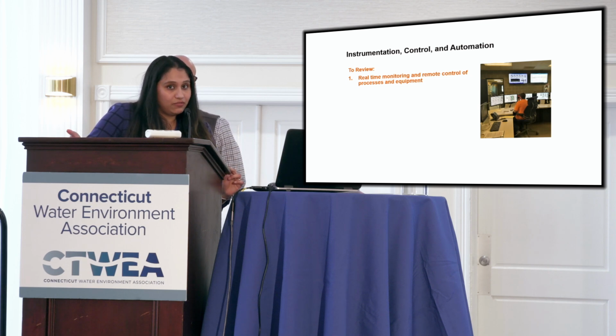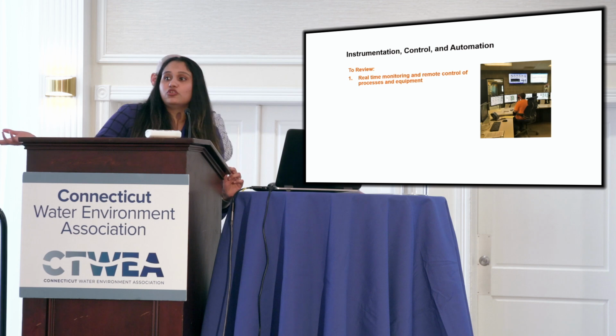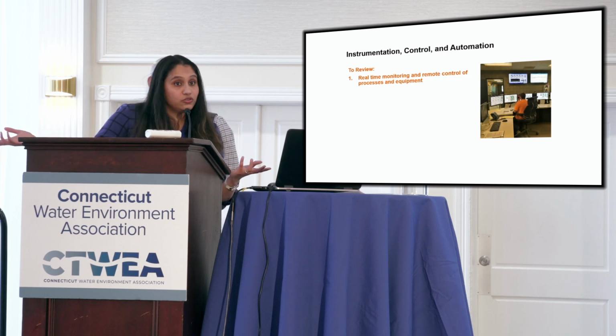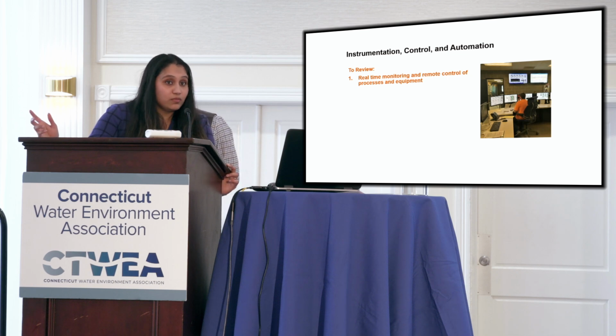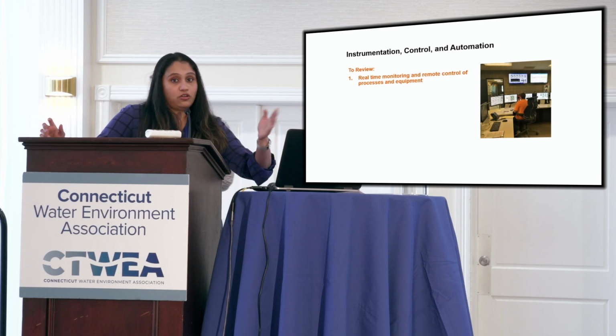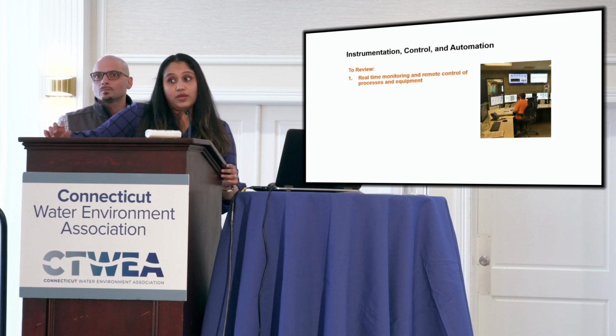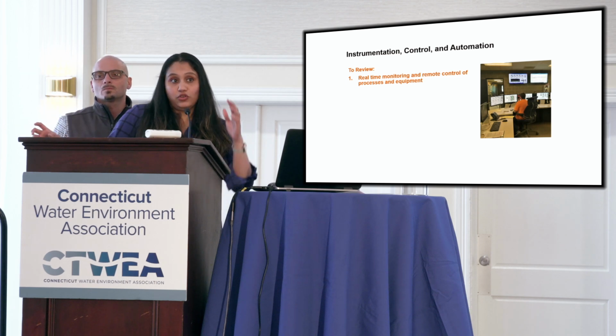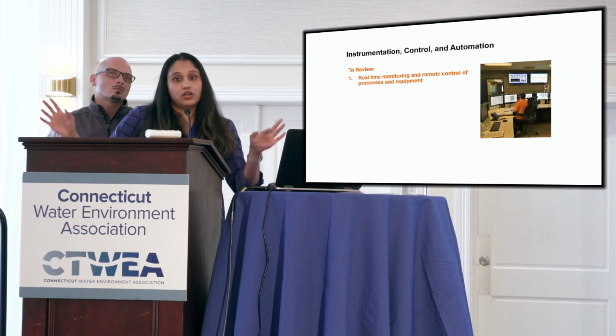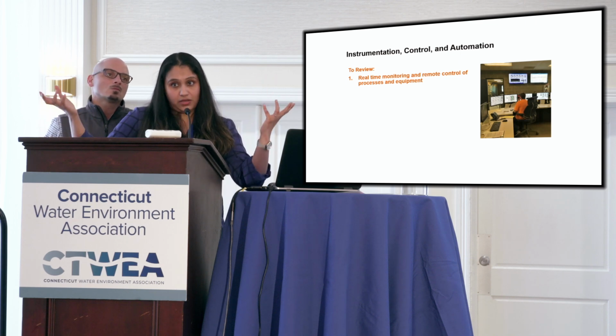Controls can be at different levels. Let's say you walk down to the pump station and turn on the pump from your local control station—that's local control. Alternatively, you walk back to your control room and operate your plant from there, or you're at pump station A and operate pump station B. All of that is done via your Scada HMI.